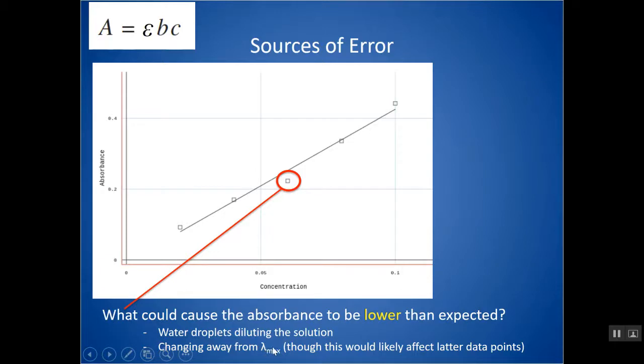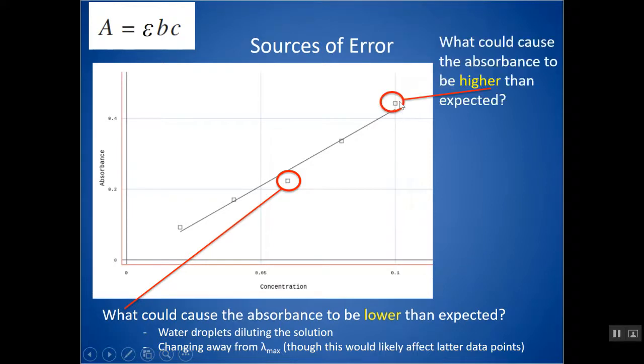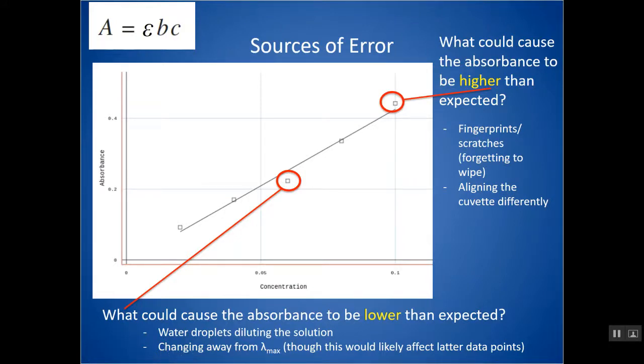If you're measuring away from the lambda max — less light would overall be absorbed. This would likely affect all later data points to also be lower, so that's probably not the source of error for one single low data point. If a data point is too high, fingerprints or scratches can absorb or scatter some light so less is detected, making it seem as if the substance is absorbing more. Not aligning the cuvette the same way — passing light through a spot with more scratches or smudges — can also cause a higher-than-expected absorbance reading.